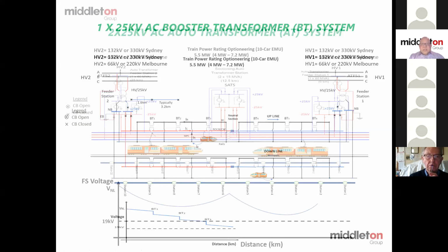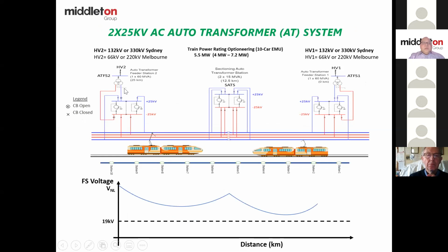Now, this is a big improvement because you're now feeding the railway with 50 kV. And these are auto transformers, so we normally have a pair. If one goes out, one is on outage, you can actually use one for both. Some systems are designed so that they're actually in parallel already, they're tied together. And you find that some systems might open the bus bars and feed from both directions.